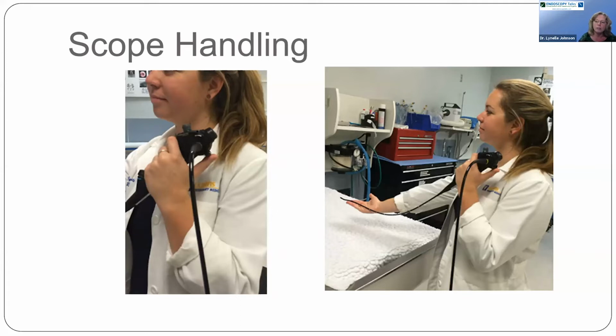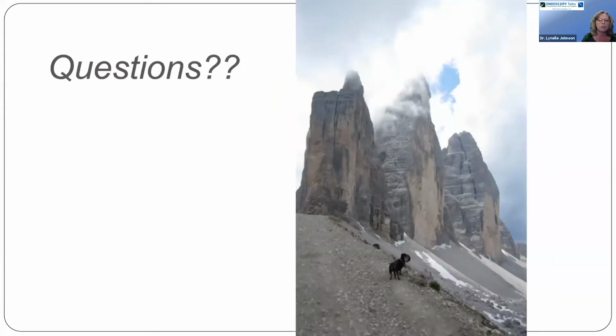One of the other things that this picture illustrates is that we always want to make sure we watch the bend in our endoscope so that we don't cause stress on the break point of the scope. There's a couple of areas of any endoscope where it can cause damage if you bend it too much. One is at the junction between the handle and the shaft of the bronchoscope, and the other is in the specialized rubber tip. So those are really important areas that we want to avoid bending. So that's what I had to talk to you about the equipment.